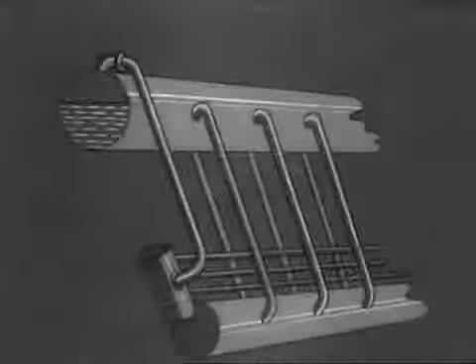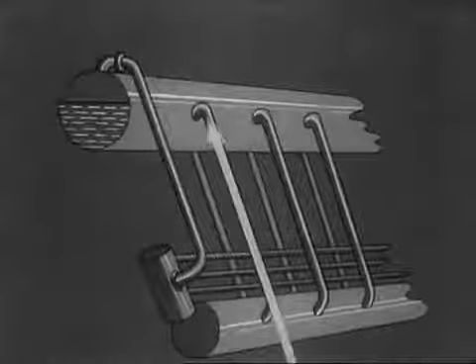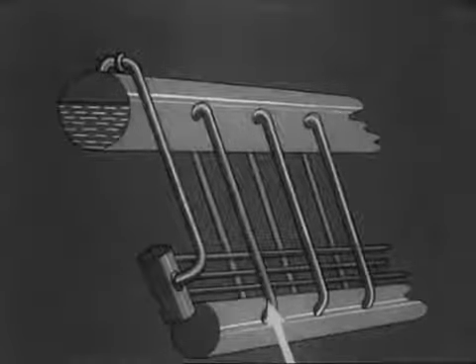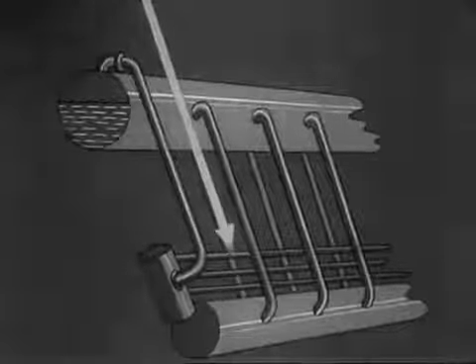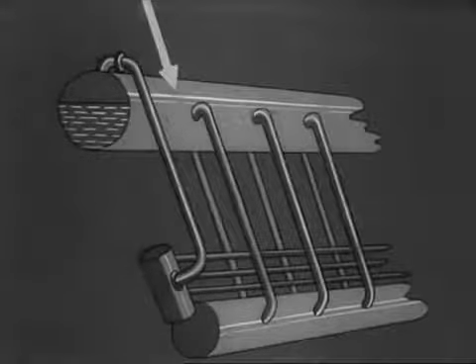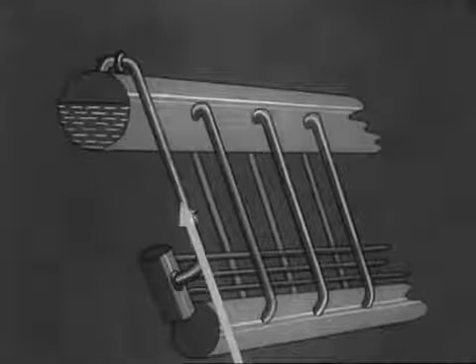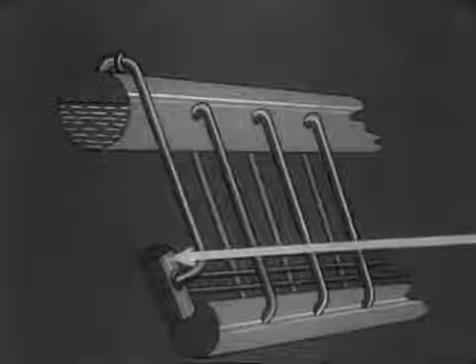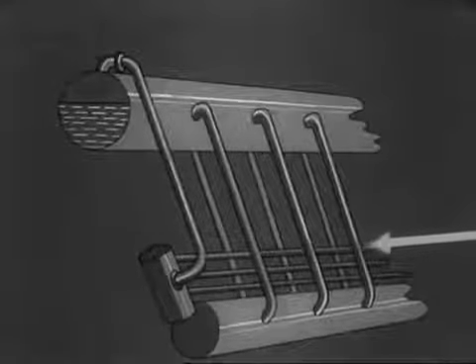Note the water level in the steam drum is normal as when steaming, but when idle it should be kept full to prevent airlocks or corrosion. The water descends through the tubes furthest from the fire into the water drums. Then it rises through the tubes nearest the fire, during which course it's converted to steam and goes into the steam drum. At this stage it's saturated or moist steam, so it passes into the superheaters, which are out of contact with water in the boiler. Here our steam is just simply cooked, and becoming dry steam passes on to the engines.